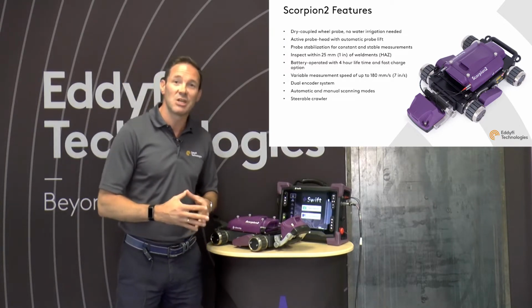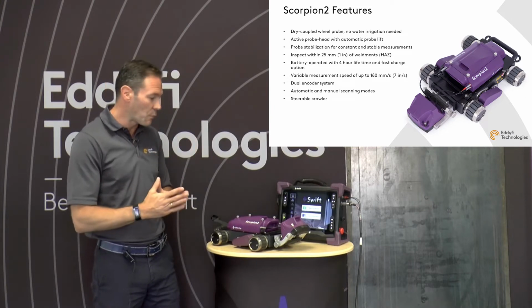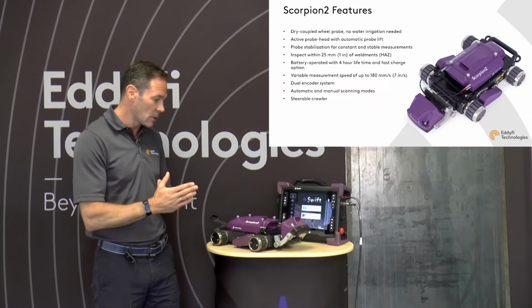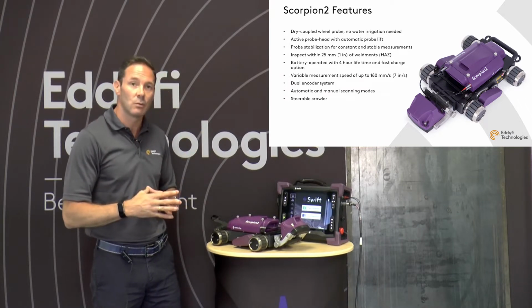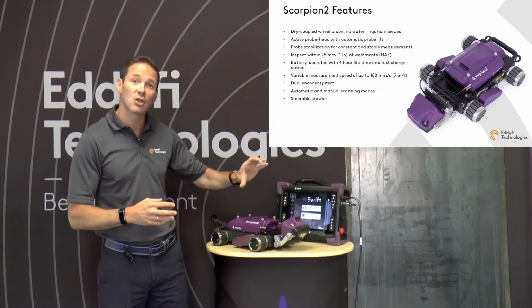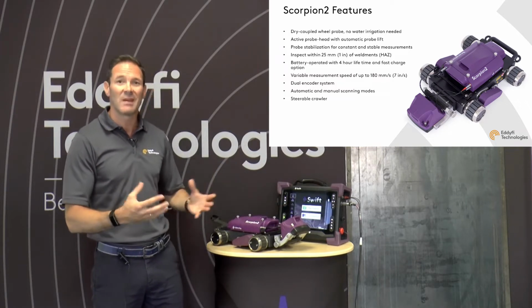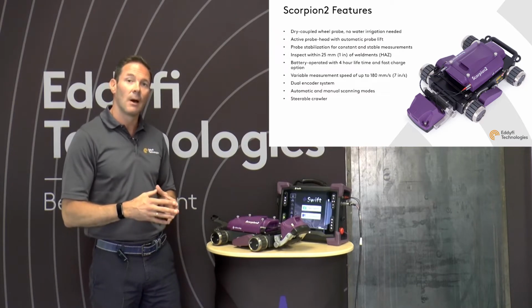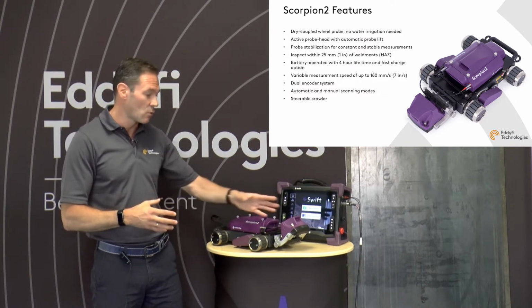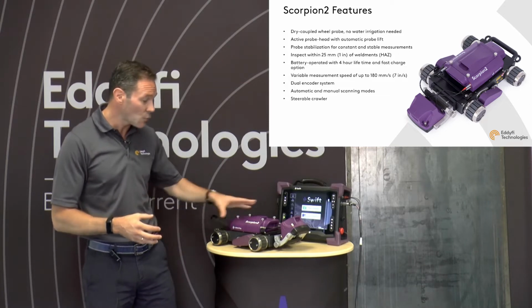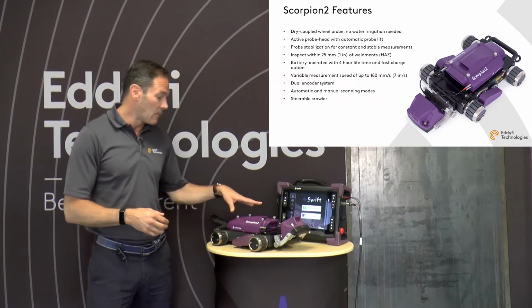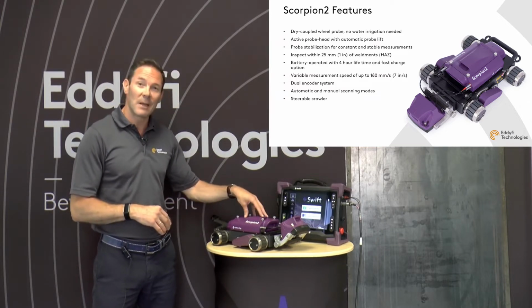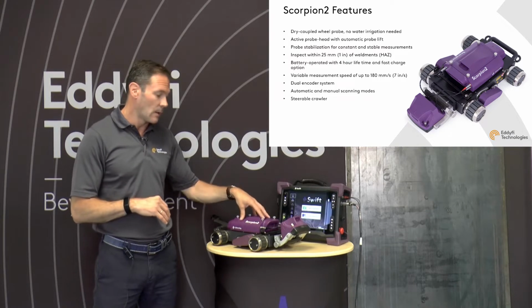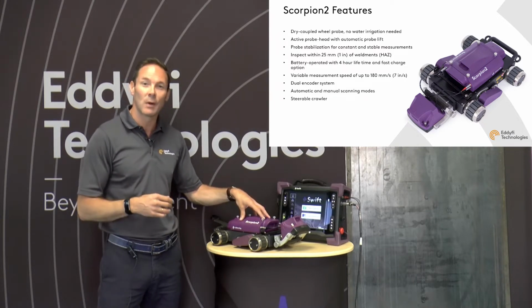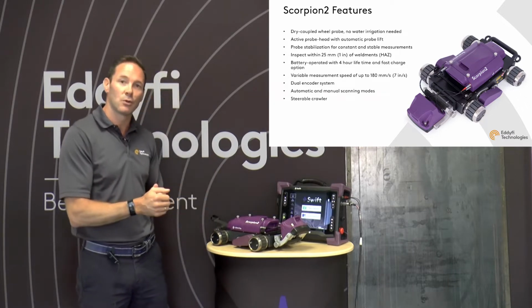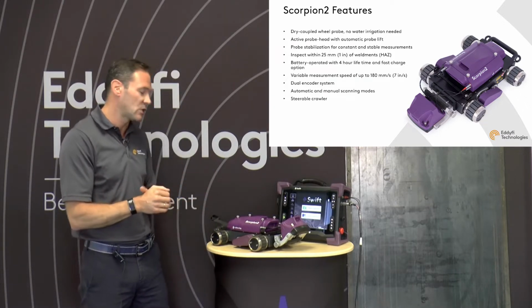Also, we have probe stabilization in this probe head, allowing for a constant probe pressure on the surface, which gives you very nice stable results when you do the measurements. The head is designed to come as close to the weld as possible. In this case, it's about 25 millimeters, and it will capture the majority of the heat affected zone while doing the inspection. The unit has its own battery supply. We supply 2 batteries with this unit, and 1 battery charge will last about 4 hours. A single charge, if you want to charge the battery again, takes about 2.5 hours. So it gives you the option to continuously run the unit throughout an inspection day.